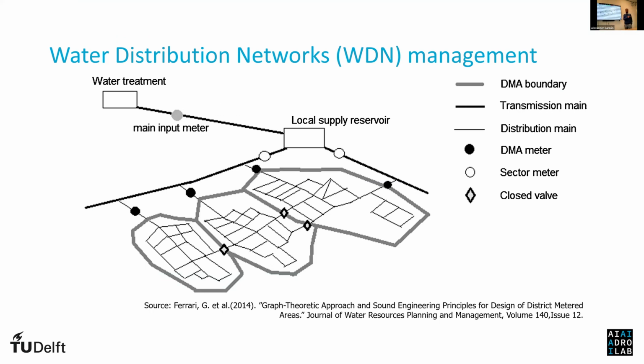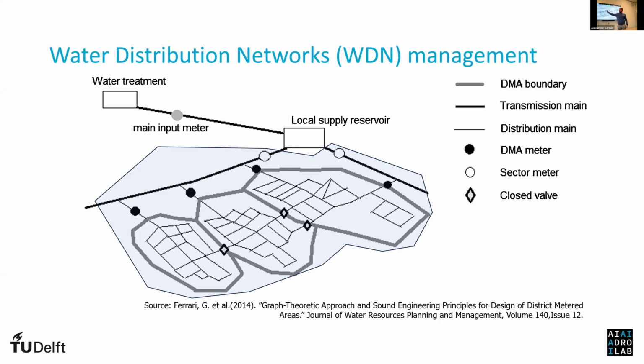You saw the water distribution system. Ricardo explained it very well. Just quickly to explain how this is managed by water companies in order to avoid leakage, and also to understand better what is happening, to direct the drinking water and understand better drinking water quality. You have the treatment, then the service reservoirs, and from the service reservoirs you have the distribution trunk mains that are going to the different areas. This area here, passing from the service reservoir up to the different distribution areas, is called a water supply zone, because it's one zone that is fed by the same service reservoir.